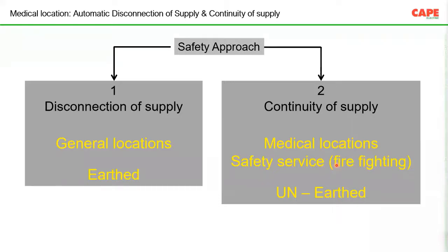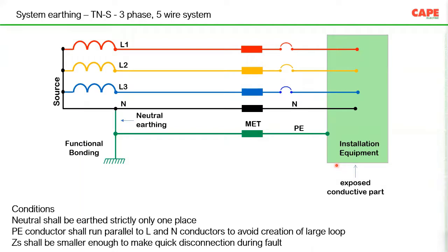So with this understanding, I'm showing you a picture which is a TN-S system. I'm sure most of the engineers attending are engineers with a medical background, and they know how the system is implemented in a typical hospital. What I am showing is a TN-S system. It means you have a source, which can be a DG or a transformer. You have the 3-phase coming from the transformer. You have the neutral, which is also distributed into your electrical installation. Now, what you should understand is, if you look at the picture, the green wire in the electrical installation is connected back to the neutral of the source.